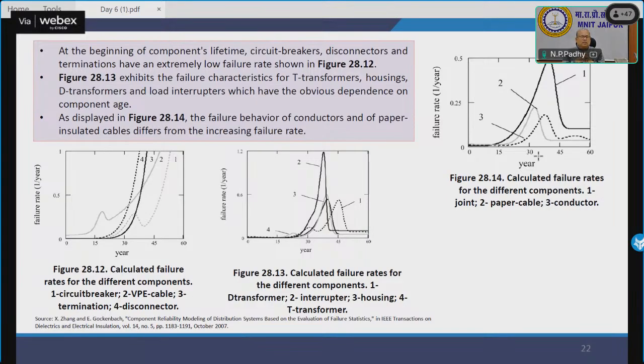Figure 28.13 shows that the characteristics of transmission transformers, distribution transformers, and load interrupters have an obvious dependence on component age. And based on figure 28.14, the failure behavior of conductors and of paper insulated cables differs from the increasing failure rate.